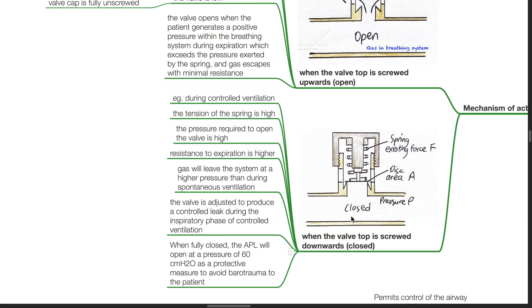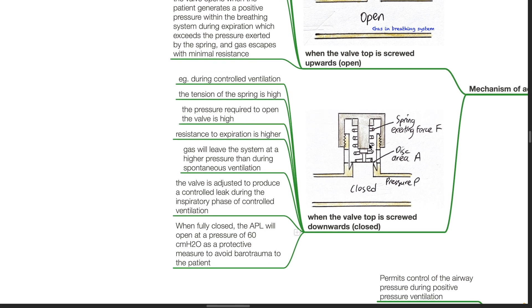When the valve top is screwed downwards, for example during controlled ventilation, the tension of the spring is high. The pressure required to open the valve is high. Resistance to expiration is greater. Gas will leave the system at a higher pressure than during spontaneous ventilation. The valve is adjusted to produce a controlled leak during the inspiratory phase of controlled ventilation. When fully closed, the APL valve will open at a pressure of 60 CMH2O as a protective measure to avoid barotrauma to the patient.